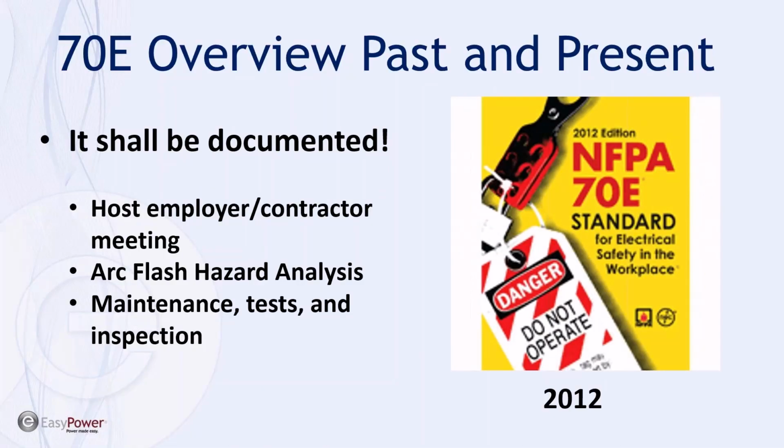2012 brought us the need to document many of the things which were in the 2009 standard. For the arc flash study or arc flash hazard analysis, having a written report was actually a requirement in 2012. So you could do a study but not have a report in 2009. That's how it laid out. But now they close the loop on that as they move forward with the various requirements in the subsequent editions.